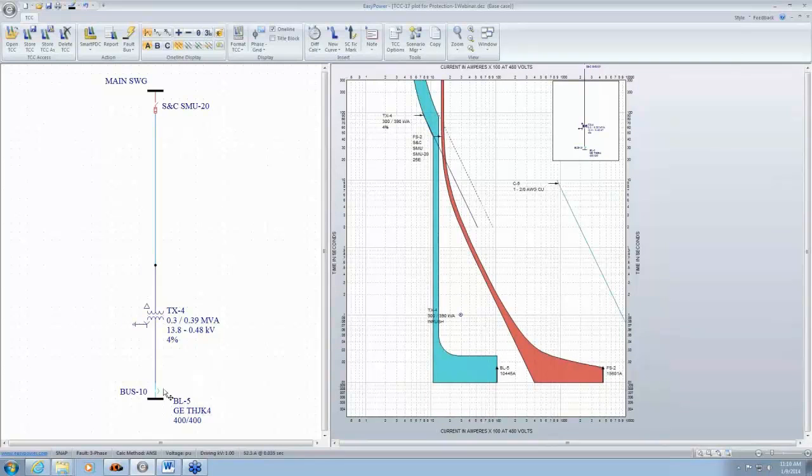In this case, typically, since these are all in line and there are no parallel breakers, you probably don't need to coordinate this fuse with this circuit breaker. But if you had multiple feeder breakers and you needed to coordinate, then we can use short circuit clipping and short circuit tick marks to help us as a coordination tool for selective coordination.